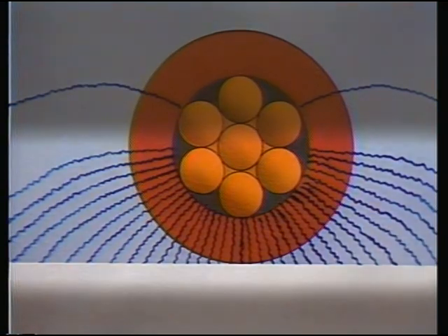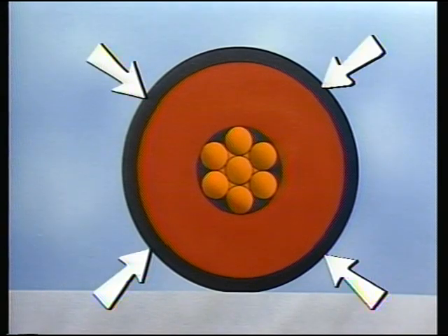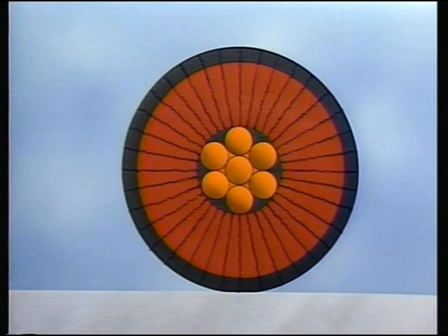This concentration is the purpose for the insulation shield layers. These layers provide a uniform ground that covers the cable insulation. You can see that with the addition of the insulation semiconductive shield layer, the stress lines are now equally distributed through the cable's insulation.